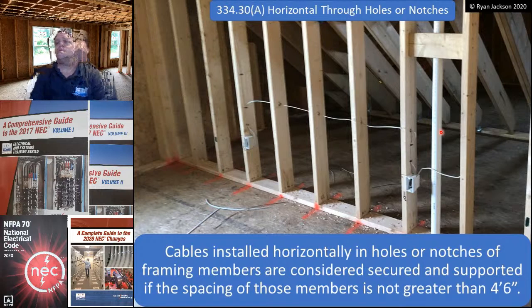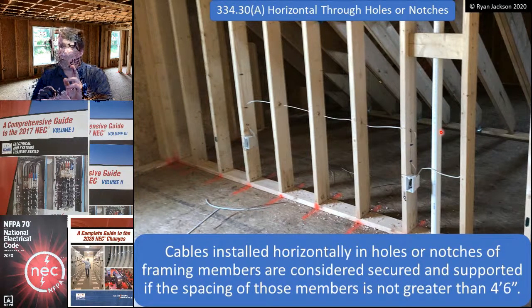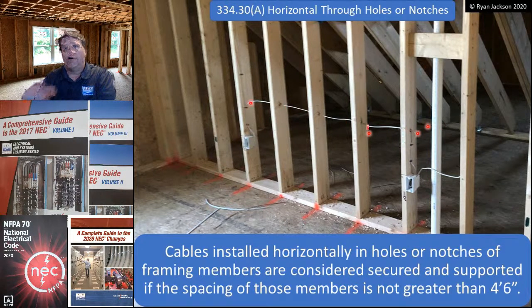Moving on, cables that are installed horizontally in holes or notches of framing members are considered both secured and supported. It's important to realize there's two rules here. Number one, have to support your cable. Number two, have to secure your cable. Two different rules. When you put it through holes in wood framing like that, through framing members, that's considered both secured and supported, as long as the spacings of the framing member don't exceed 4'6". But you still have to secure it within 12 inches of the box. So be careful on that.